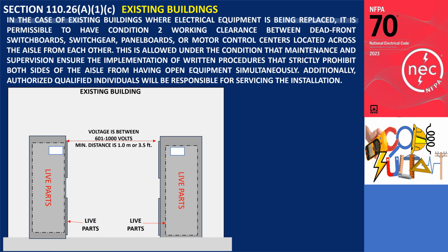In the case of existing buildings where electrical equipment is being replaced, it is permissible to have condition 2 working clearance between dead front switchboards, switchgear, panel boards, or motor control centers located across the aisle from each other. This is allowed under the condition that maintenance and supervision ensure the implementation of written procedures that strictly prohibit both sides of the aisle from having open equipment simultaneously. Additionally, authorized qualified individuals will be responsible for servicing the installation.